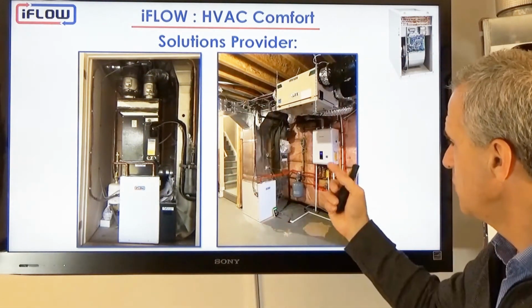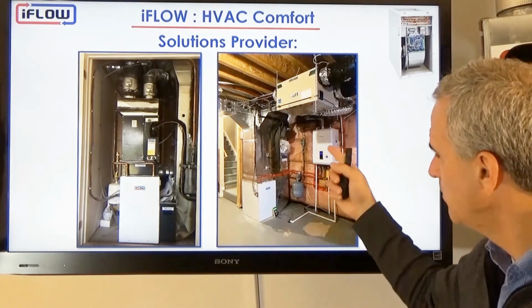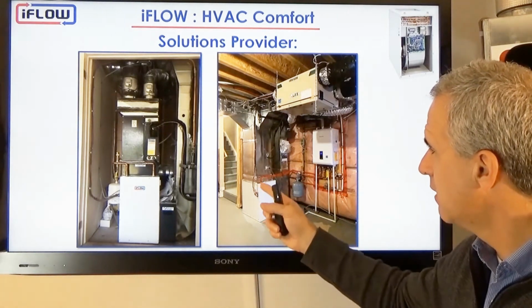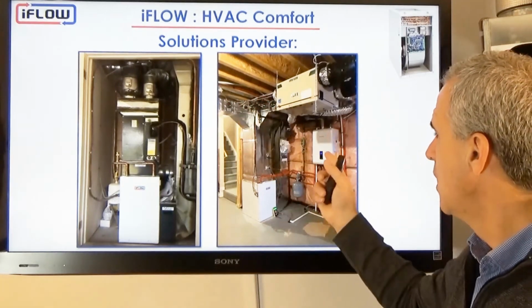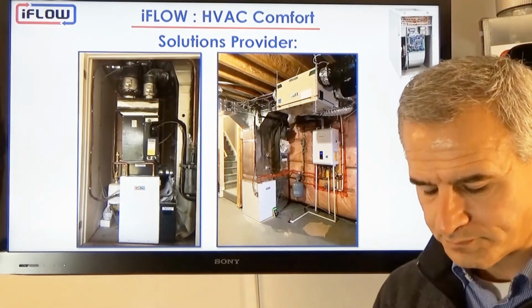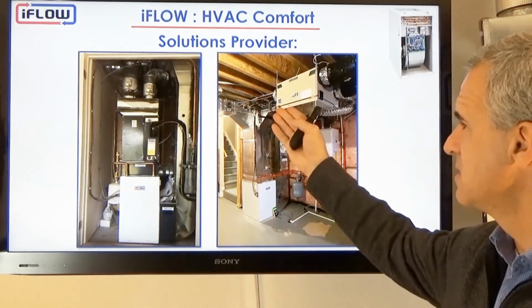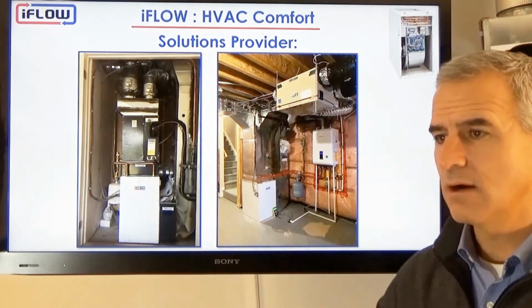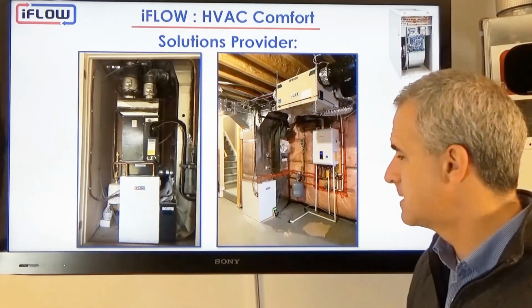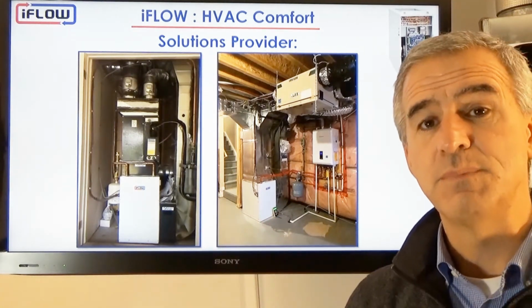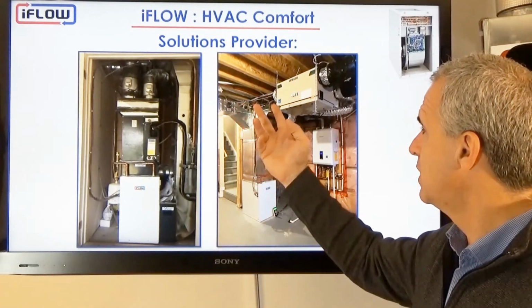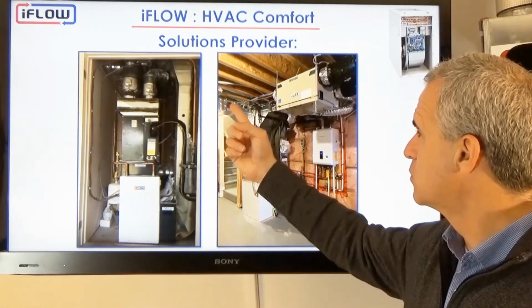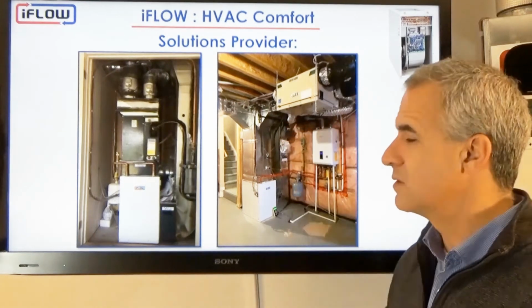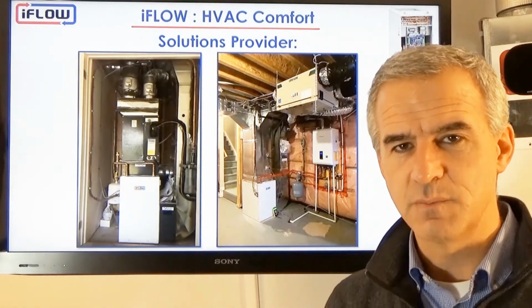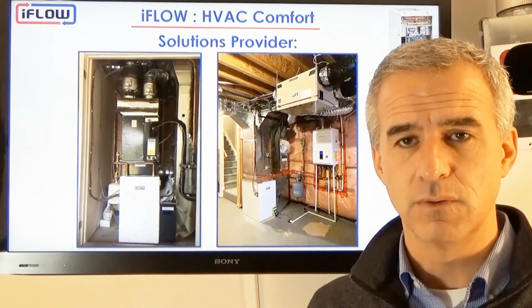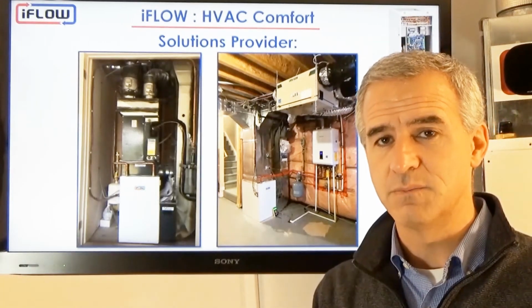This final application that we've got here is another wall-hung boiler feeding over into our air handler and zoning as well. So why use a boiler? Well, for example, let's say we see this is zoned. Let's say our heat loss in this new home is 30,000 BTUs. And let's just assume we have 3 zones. So here's 1 zone, there's 2 zones, let's assume there's another zone. So we have 3 zones, 30,000 BTUs divided into 3 zones, and let's say they're equal zones. So each zone requires 10,000 BTUs.